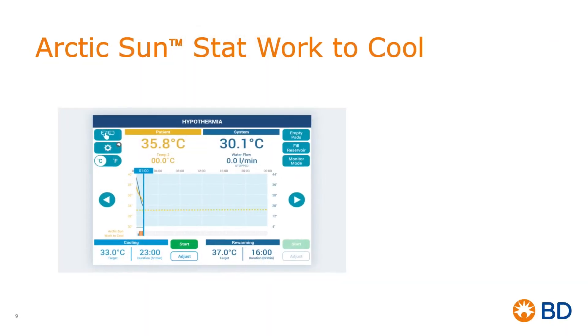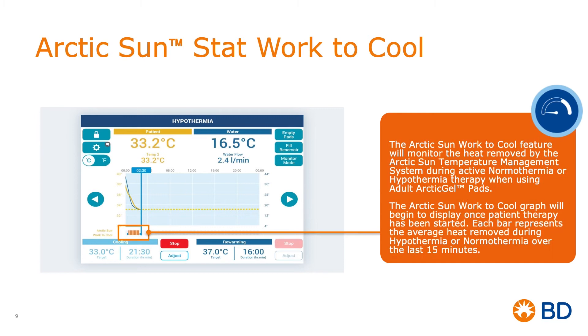Question: how can I assess my patient for heat generation? Work2Cool continuously monitors fluctuations in water temperature to indicate when your patient may be generating heat. The Work2Cool information displayed at the bottom of the therapy graph can show average heat removed by the patient throughout therapy. When the gauge is displaying blue, it is an indication that the system is not working too hard and the patient should be monitored as normal.